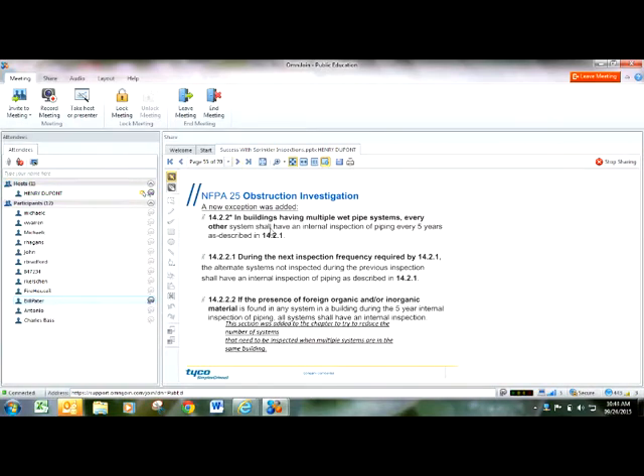Now, I do agree with this other statement that they make, let me see, where is it? If you have buildings with multiple systems, say you've got a warehouse with 6 or 7 sprinkler systems in it, NFPA 25 2013 edition says you're allowed to do an obstruction investigation on every other system. When the next 5 years roll around, then you inspect the systems that weren't inspected. This is just to help building owners save a little bit of money, because if you have a building with multiple systems, it can get pricey to do these 5-year obstruction investigations on every single system.